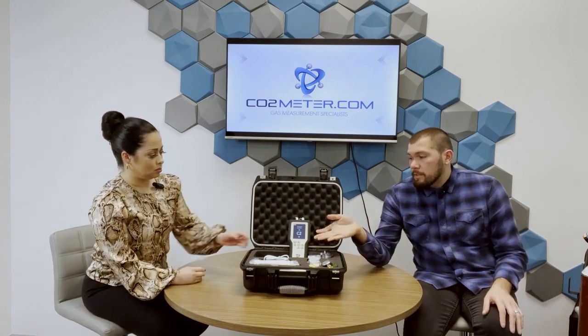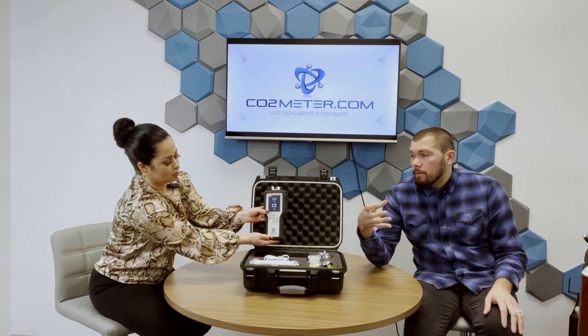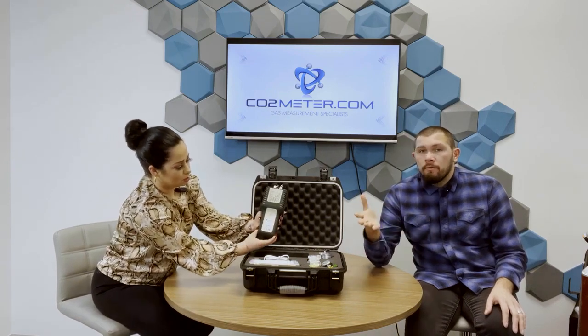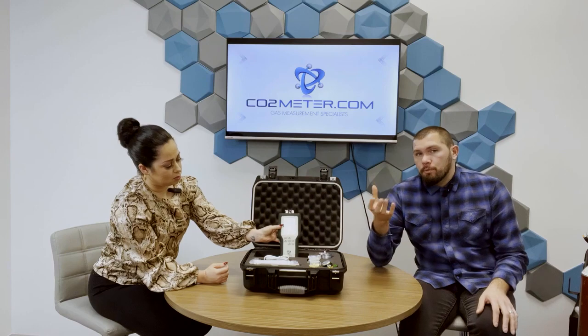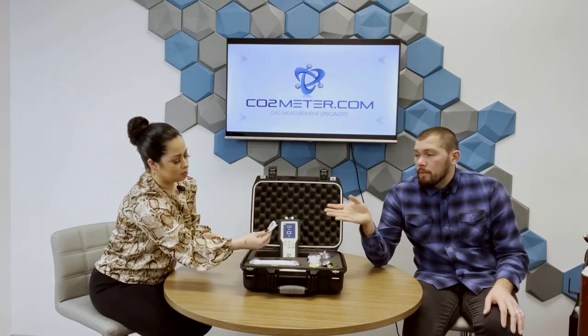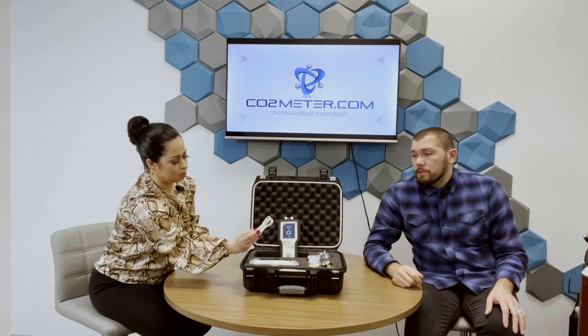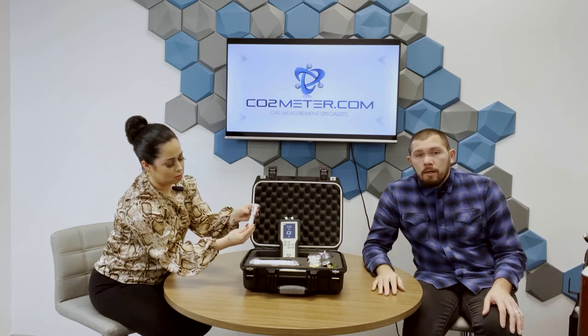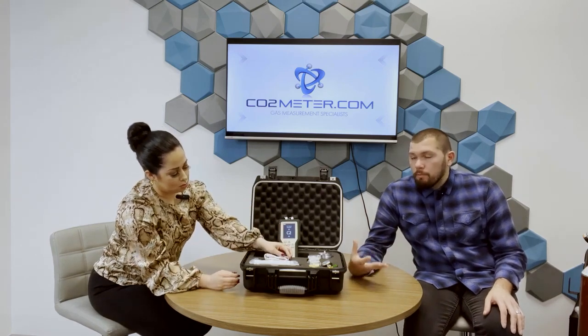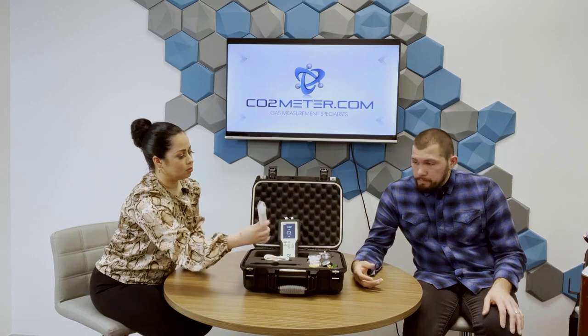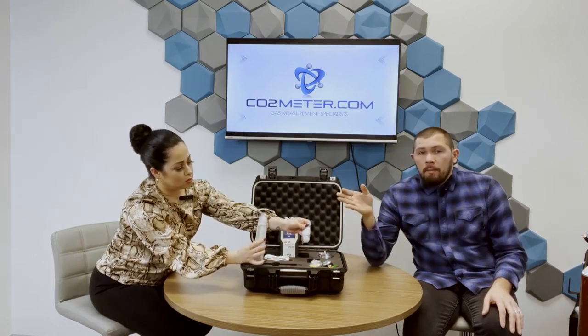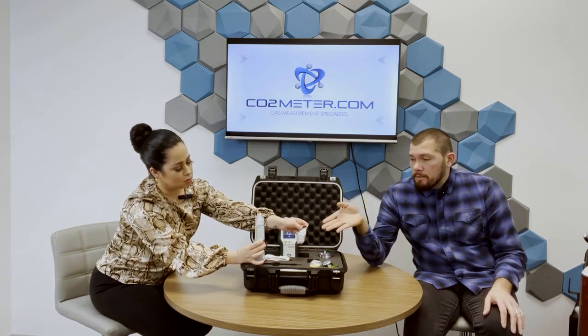So next, you will obviously see the device, which is housed in a rubber enclosure to give a little more added protection during actual use. Next, it comes with that charging cable, which is a USB cable, so anywhere you have access to a USB port, you can recharge your device. We've included some extra filtration, a water trap, and some particle filters. That way you really protect your device. Anything that's flowing in your gas sample, make sure that it doesn't get sucked into those sensors within the device.